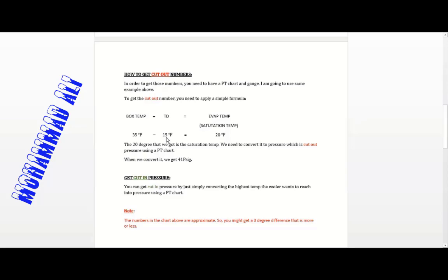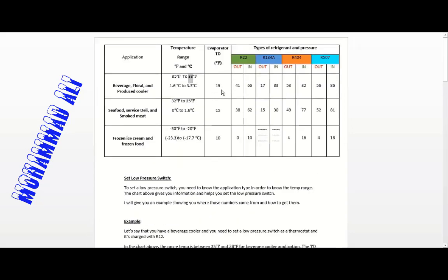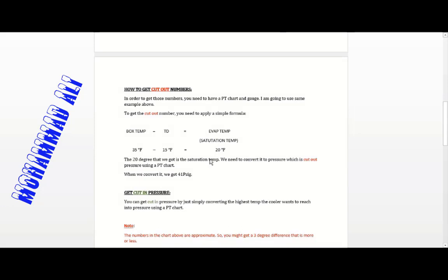We subtract the TD of 15°F from 35°F, giving us 20°F evaporator or saturation temperature — this is the coil temperature. But since it's a low pressure switch, it doesn't sense temperature; it only knows pressure. So we need to convert this 20°F temperature into a pressure value.